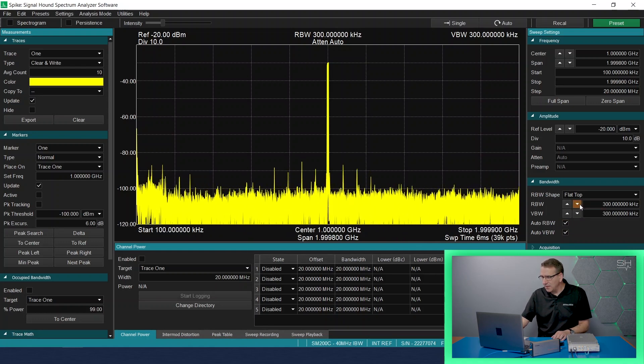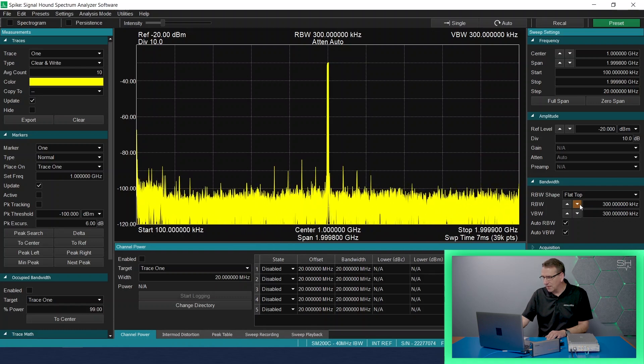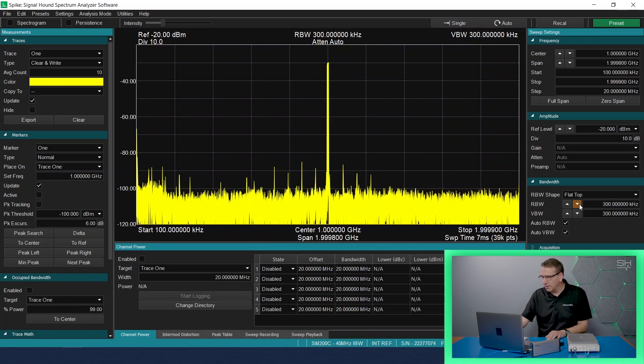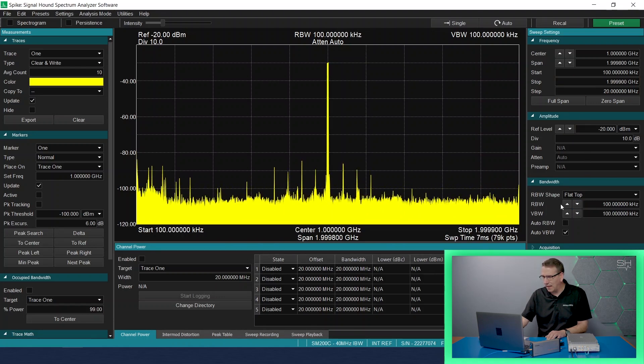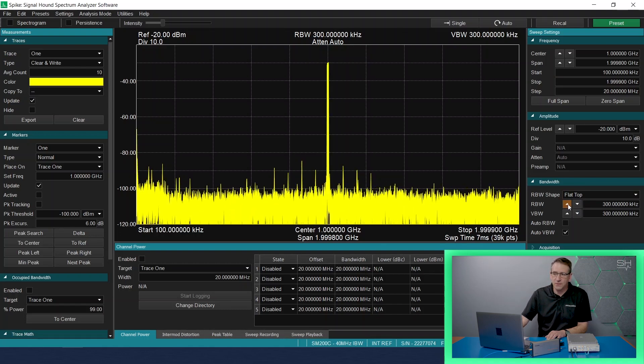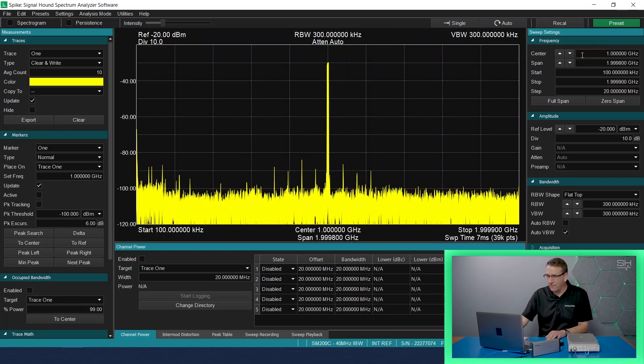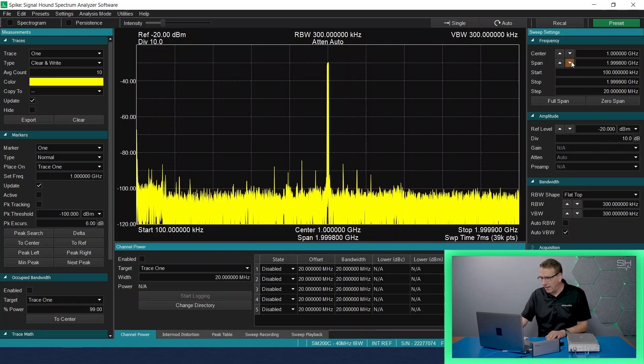As you can see, I can leave the resolution bandwidth set at 300 kilohertz and then just decrease the span, and we can resolve the multiple signals that I have close together in that frame.